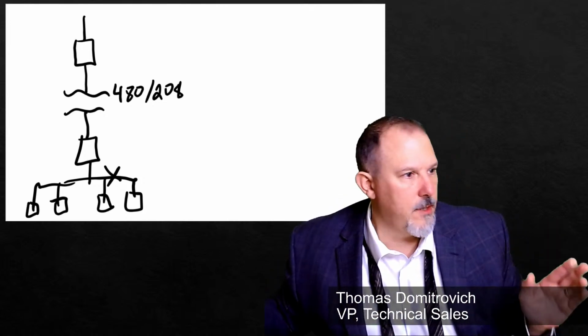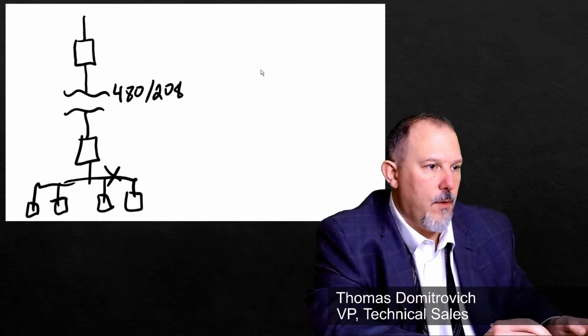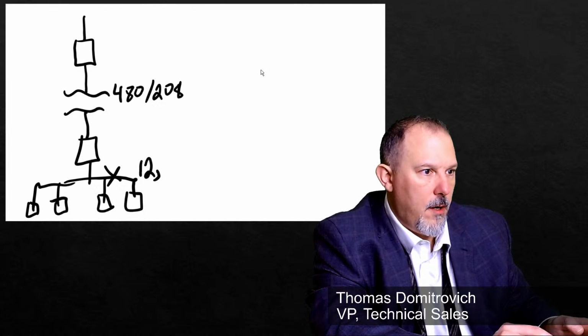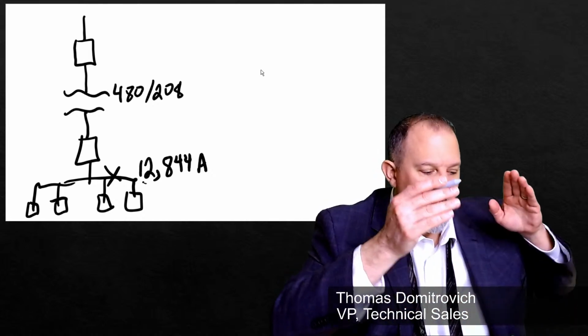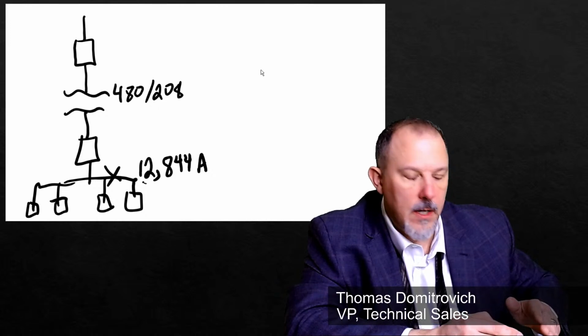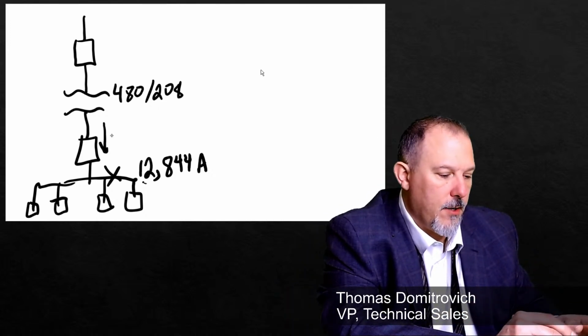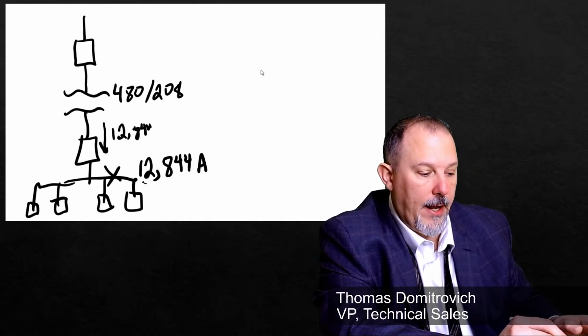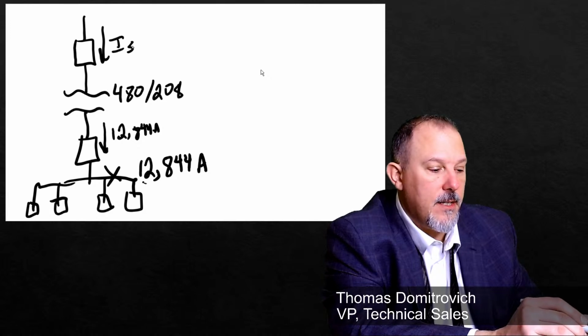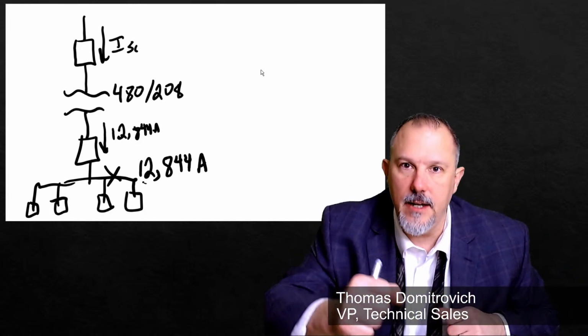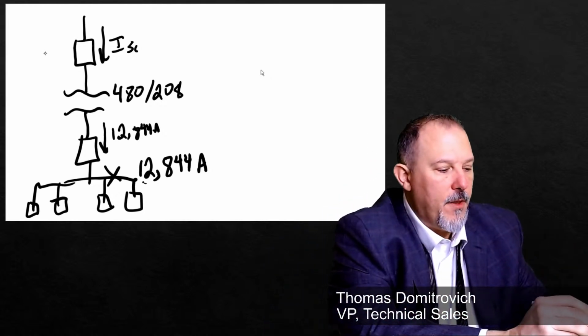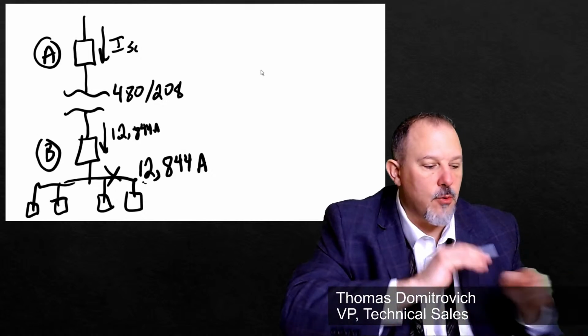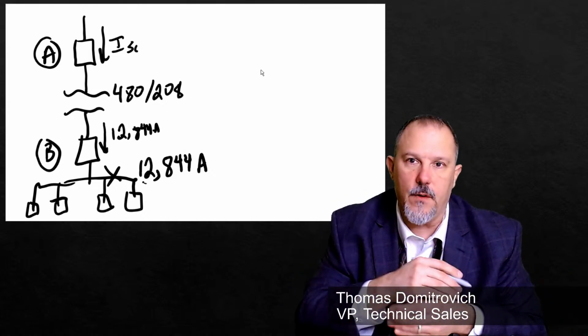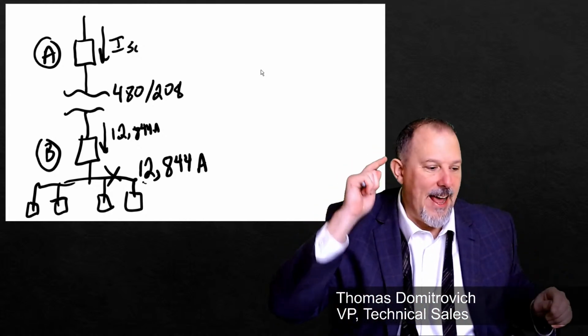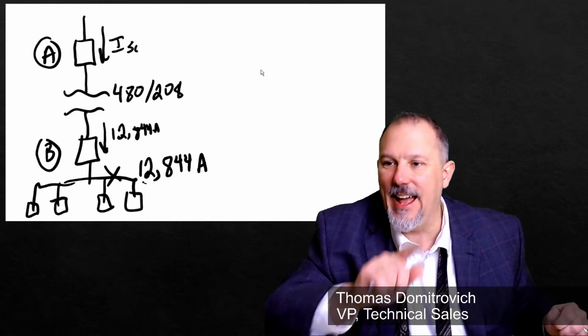What's the fault current on the secondary? We're going to use the numbers. We'll say 12,844 amps. Okay, so that three-phase bolted fault current at this point in the power system is 12,844 amps. So this breaker is going to see 12,844 amps. What current does that breaker see for that fault downstream? Does the primary breaker, I'll call it A, see 12,844 amps of fault current during this fault on the secondary? We got an approximate half, right?